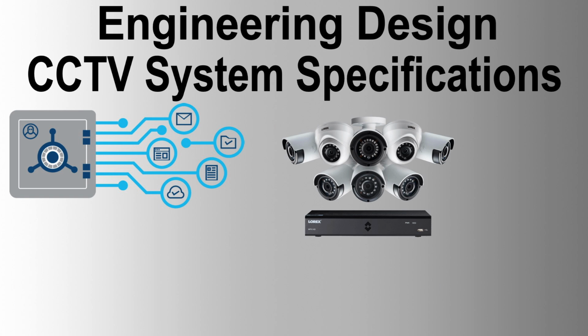CCTV operator stations. General: the master CCTV operator station shall be located at the MCR at the main pumping station, and backup CCTV operator stations at the alternate control room at the main oil terminal. CCTV monitors are located at the control room at the intermediate pumping station, capable of viewing only assigned cameras located in intermediate pumping station areas. Functionality: the CCTV operator station shall provide capability for image viewing, sequential switching, camera selection, and pan, tilt, and zoom control of each camera. Components: each CCTV operator station shall have 2 sets of system cabinets, monitors, and keyboard controllers.